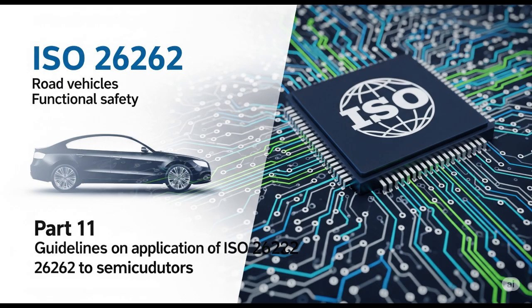Yeah. You could have data corruption, right, where critical values, say sensor readings or calculations, are simply incorrect, leading to miscalculations, or accessing unintended locations, which could compromise security or simply lead to system crashes. Other examples include deadlock or livelock, where a system gets stuck processing something infinitely, or incorrect instruction execution. The standard actually provides examples like CPU-FM, CPU failure modes, DMA-FM, SRAM-RWFM, memory read-write failure modes. These clearly articulate the functional impact, the real-world consequences of these tiny silicon flaws.